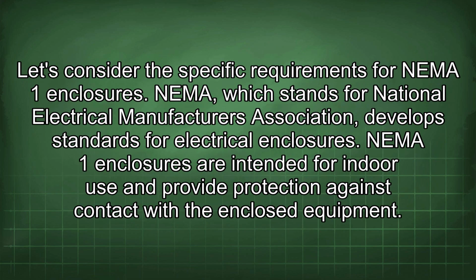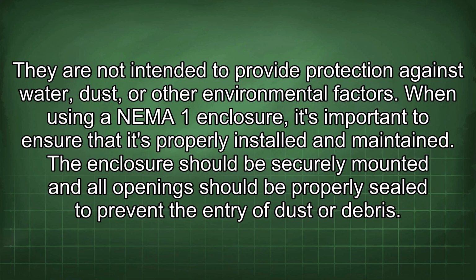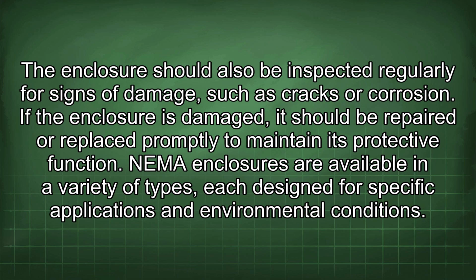Let's consider the specific requirements for NEMA 1 enclosures. NEMA, which stands for National Electrical Manufacturers Association, develops standards for electrical enclosures. NEMA 1 enclosures are intended for indoor use and provide protection against contact with the enclosed equipment. They are not intended to provide protection against water, dust, or other environmental factors. When using a NEMA 1 enclosure, it's important to ensure that it's properly installed and maintained. The enclosure should be securely mounted and all openings should be properly sealed to prevent the entry of dust or debris. The enclosure should also be inspected regularly for signs of damage, such as cracks or corrosion. If the enclosure is damaged, it should be repaired or replaced promptly to maintain its protective function.